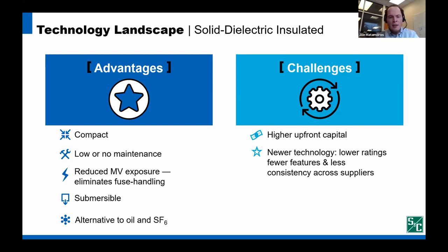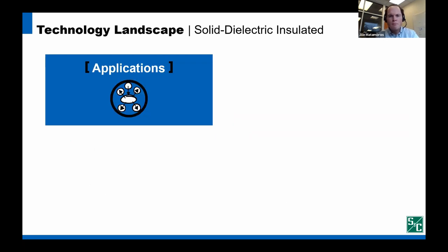Using SD can be a challenge to existing work practices, which require three position switchgear. And in air, oil, or gas insulated systems, a user can better assess the insulation system health, since those use self-restoring insulation systems versus solid dielectric, which doesn't really have an analogous state indication on insulation health that you would see in a gas gauge or oil quality test. And so with that, let's see where solid dielectric can be best applied.